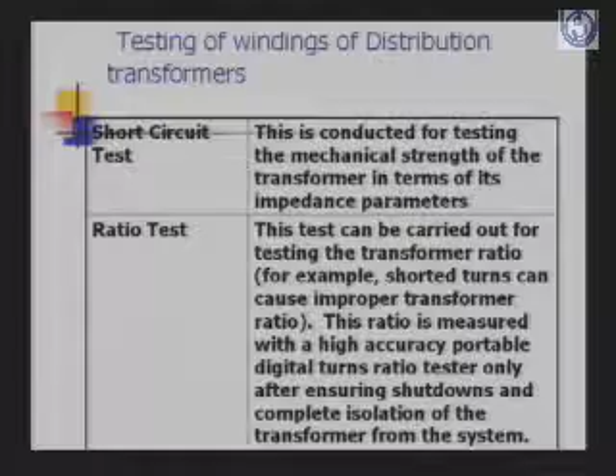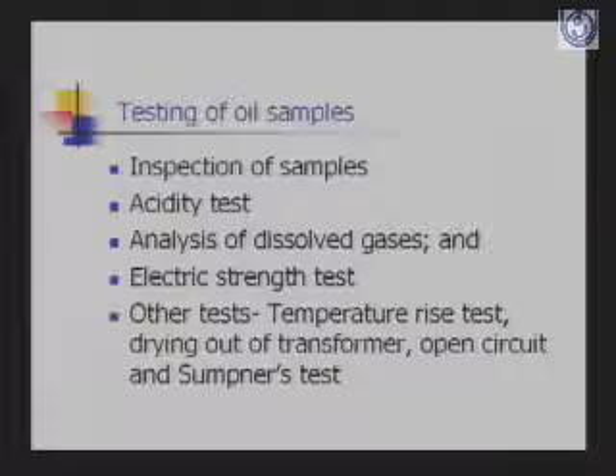Testing of oil samples. Oil is a very important insulating material for the distribution transformer as well as the power transformer. So we should be testing the oil as per IS 335. You do an inspection of the sample, you conduct an acidity test, you conduct an analysis of dissolved gases, an electric strength test, and there are some other tests also like temperature rise test, drying out of the transformer, open circuit and Sumpner's test.